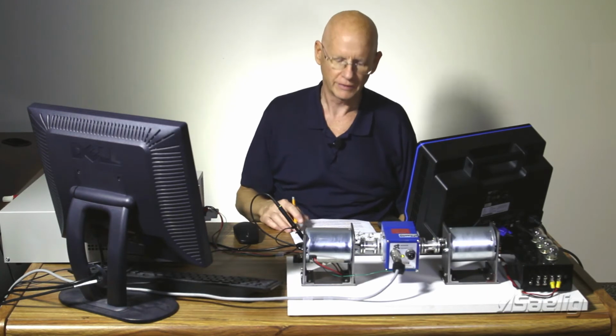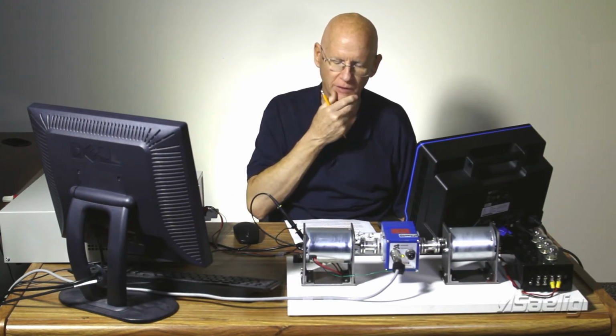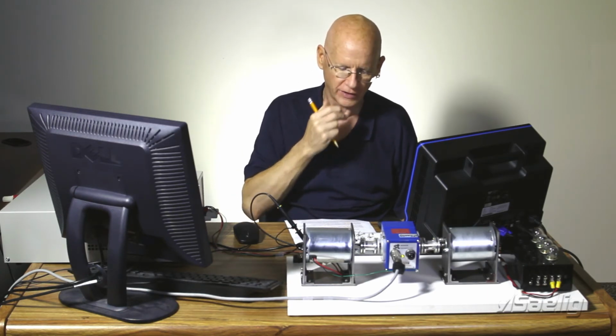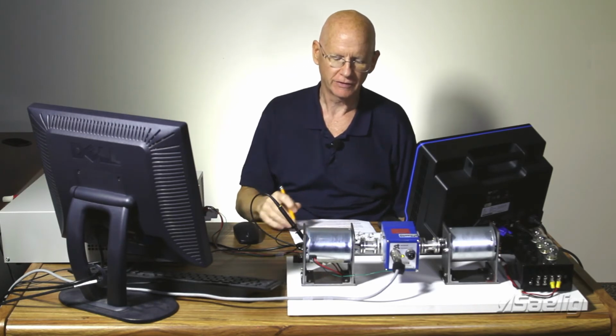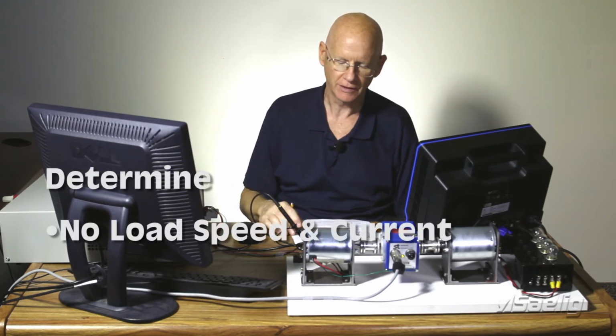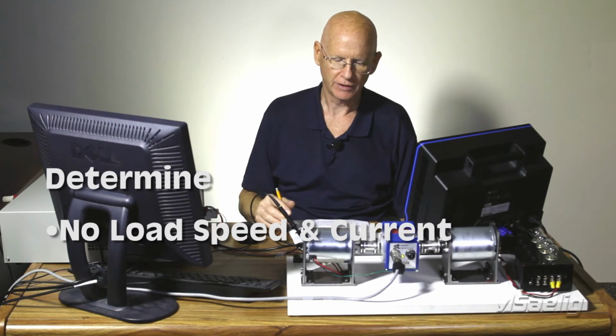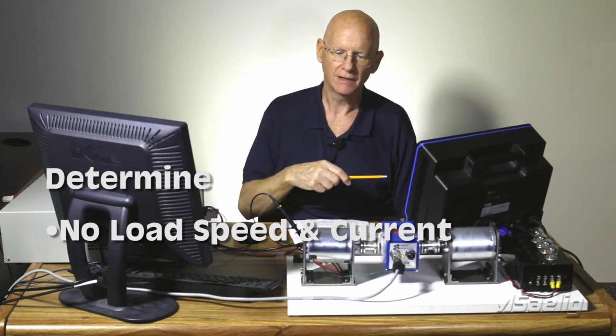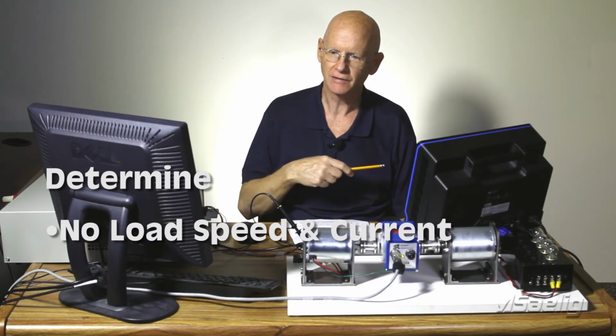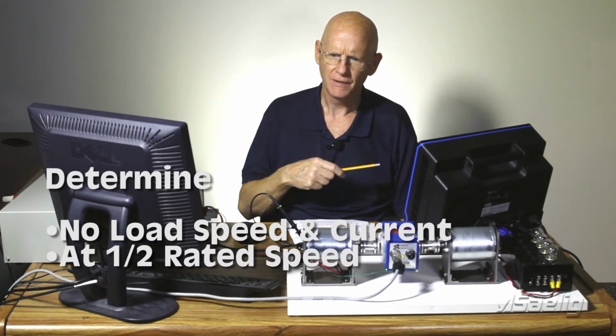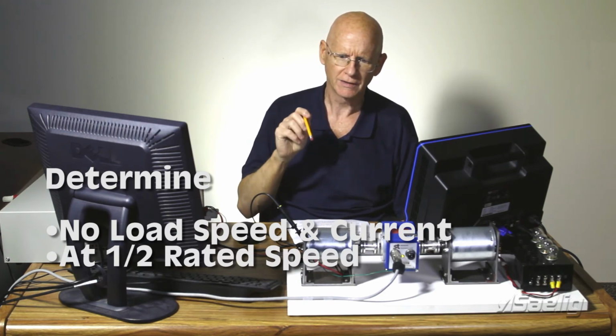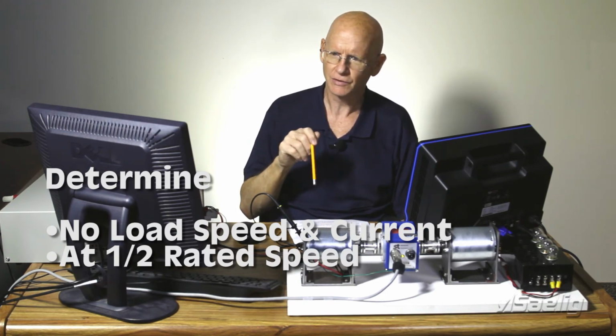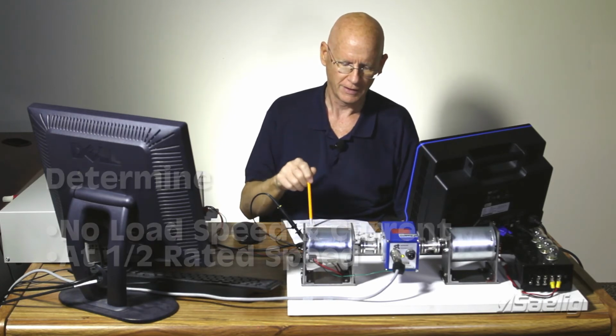So what are we going to do with it? We're going to determine the following on this drive motor. The first thing we're going to do is check the no load speed and current, and we're going to operate the unit at approximately half its speed, which, as you know, is where a permanent magnet DC motor develops its most power.